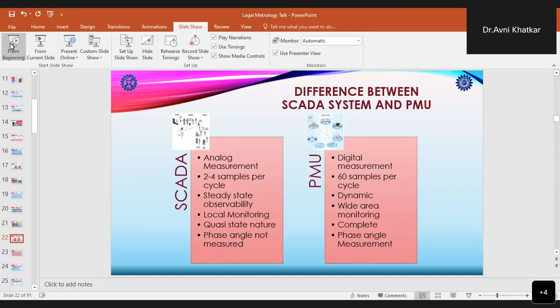And the PMU data which is collected can be used efficiently by the grid operators to monitor the real-time grid conditions and the phase angles so that we can optimize and push more power through the existing transmission lines and transformers. Hence, by using precise load balancing techniques, we can use the existing infrastructure to its maximum capacity. So by using a PMU, we are also getting a wide area monitoring system. So we are getting early warnings about our asset conditions, and a complete stability picture of the grid is there if we are using phasor measurement units.